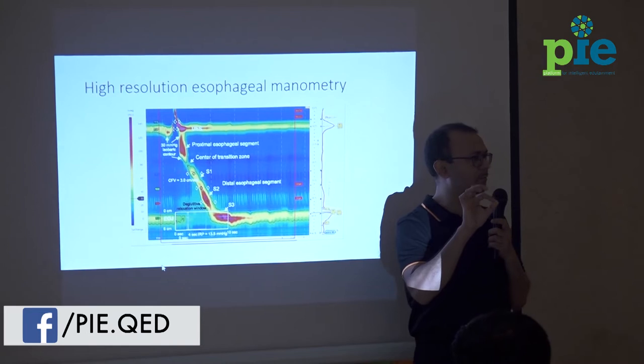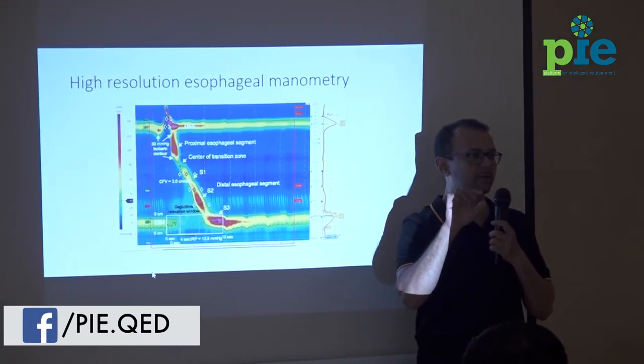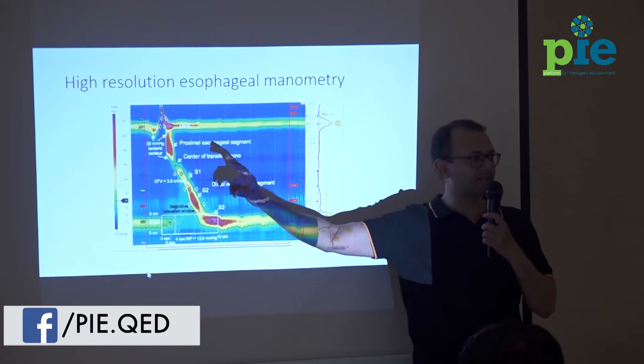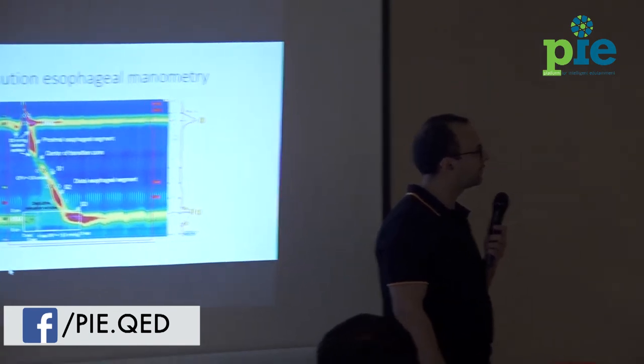So every channel has a sensor, it measures the pressure. Essentially, this is like a pixel of your computer. Every time there's a change in the pressure, there's a pixel which goes up and measures the pressure. So all the 16 channels will measure the pressure difference. So the transducer is placed once.